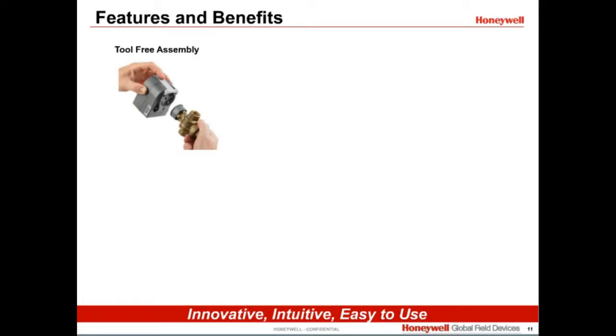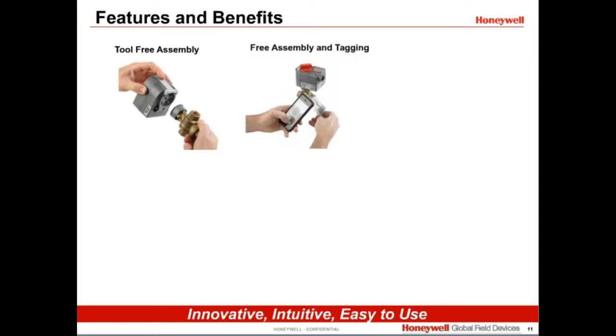The VBN is installed by simply snapping the actuator onto the valve. No tools are required. It can be mounted in any of 4 orientations, either parallel or perpendicular to the valve. To remove the VBN from the valve, simply press the light gray lever to release the actuator from the valve. The valve and actuator can be ordered as an assembly and can be tagged with information about the valve and actuator. It also includes a QR code that can be scanned on your smartphone to view the online instructions.